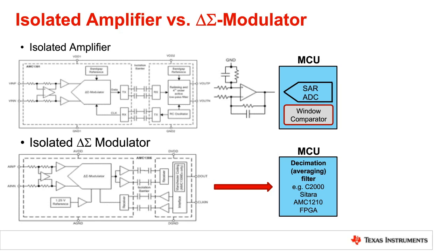And then we have that isolation barrier, which on the newer devices is double stack capacitive, which can even get up to reinforced isolation. So we're looking at common mode capabilities in the 1.5 kilovolt range for a design like this.